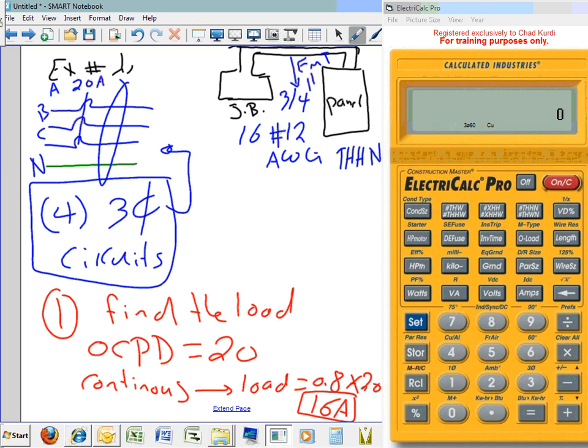Everybody agrees on that one? Based on continuous load, my load cannot be out of this circuit more than 20 amps. Okay, cool? So I'm limited to 16 amps from the get-go on this circuit breaker. Now my problem is I decided to group them together and put them in a conduit. So I have another issue. What's the other issue? Grouping, bundling. Okay, so I have a bundling problem.